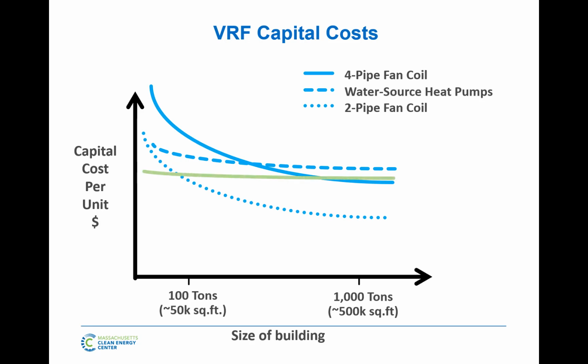Then if we look at this green line here, this is where VRF comes in. And what's very interesting about VRF is that it's a completely modular system. If I'm doing a 100-ton building, I'm probably using 5 20-ton systems. If I'm doing a 1,000-ton building, I'm probably using all those same 20-ton systems, just significantly more of them. So your capital cost per unit is going to be consistent across the board. If you look at a 20-suite office building, its cost per office is going to be the same whether there's 100 of them or 1,000 of them, because you're just adding a system. It's modular, whereas you don't have those upfront capital costs.